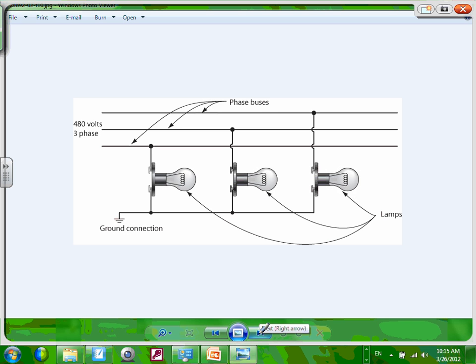You have an assembly line where you take a cow from this side, canned beef from the other side. That's the system. Steel from this side, a car or a truck from the other side, that's a process. They allow you to use an ungrounded system with this. Meaning, if you have a short circuit on ground, one phase, that's the beauty of an ungrounded system. You have the first hit on phase A, you're still standing.